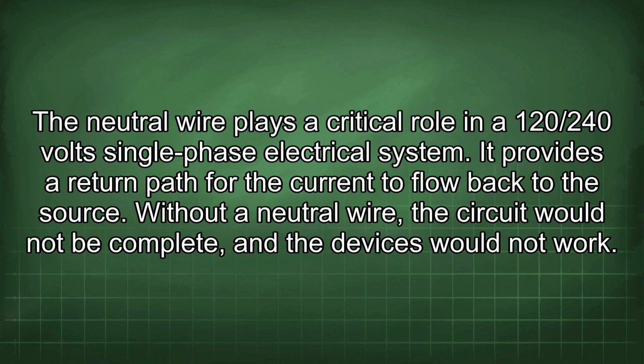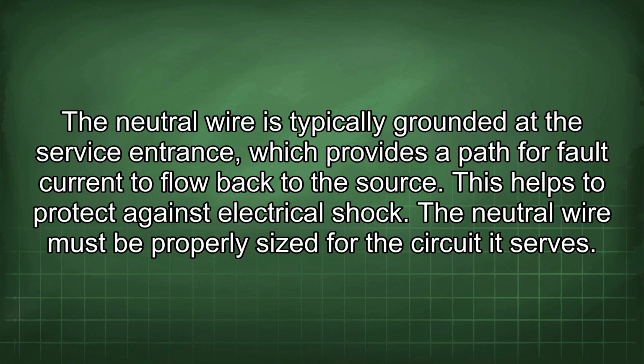The neutral wire plays a critical role in a 120/240 volt single-phase electrical system. It provides a return path for the current to flow back to the source. Without a neutral wire, the circuit would not be complete and the devices would not work. The neutral wire is typically grounded at the service entrance, which provides a path for fault current to flow back to the source. This helps to protect against electrical shock. The neutral wire must be properly sized for the circuit it serves.